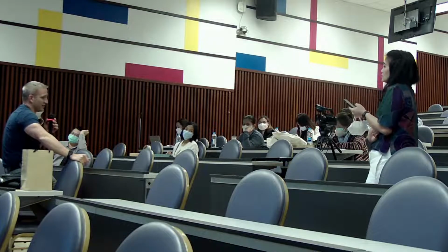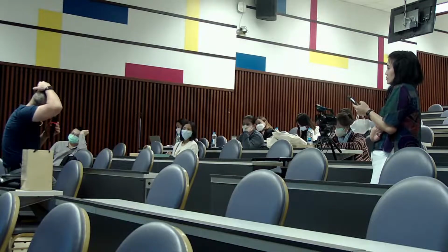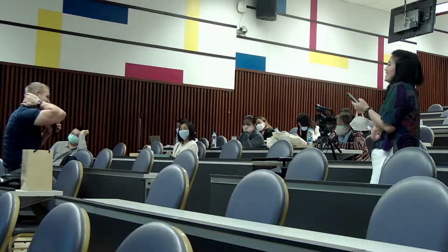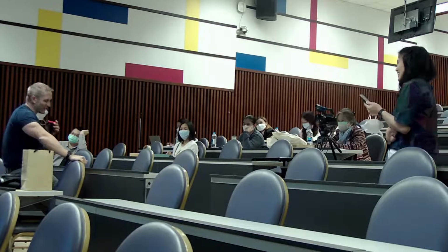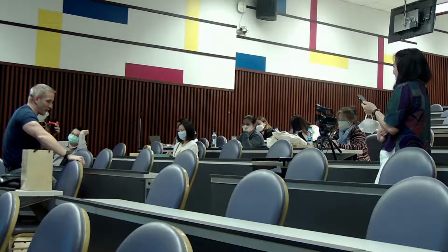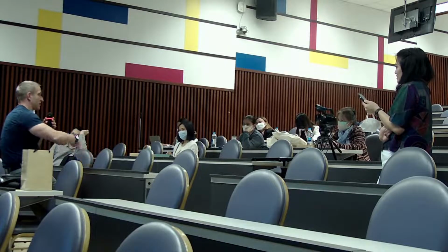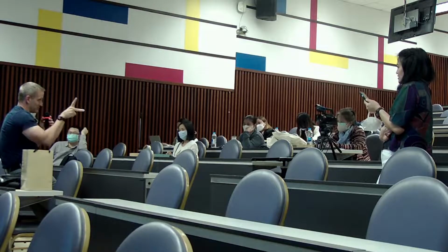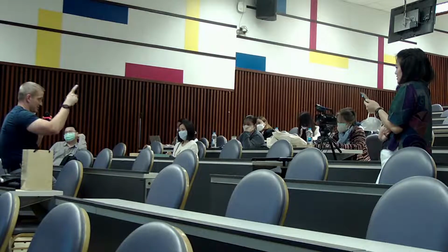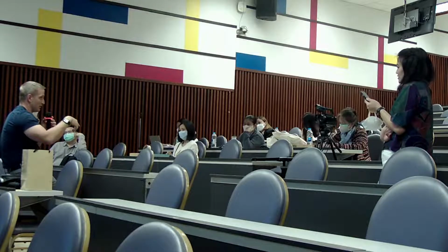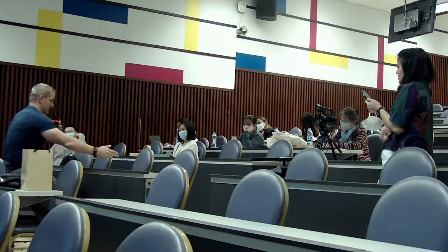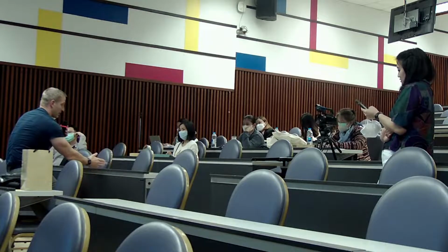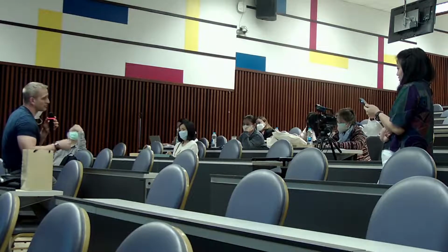We just sent in a proposal to the IEC, and if it gets accepted, it'll take us 10 years to come up with the standards. So don't hold your breath. It's not going to come fast. But right now, the question was, on a fast switch or a two-tube as it spins, do you just calculate CTDI as an aggregate of the two? Generally, what I do is look at each of the kV stations. If I know my CTDI is accurate for all my kV stations, I'm happy with that, personally.